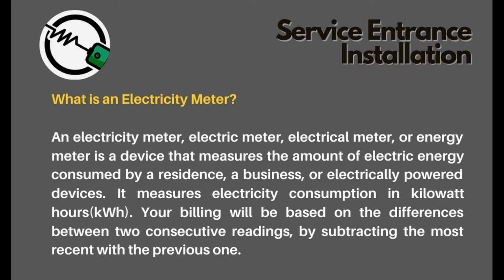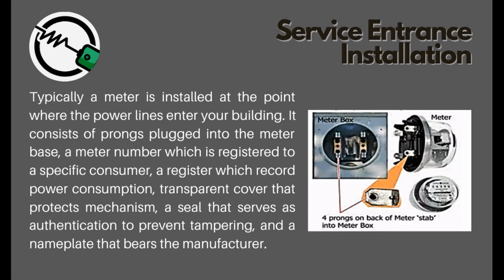Your billing will be based on the differences between two consecutive readings, by subtracting the most recent from the previous one. Typically, a meter is installed at the point where the power lines enter your building. It consists of prongs plugged into the meter base, a meter number which is registered to a specific consumer, a register which records power consumption, a transparent cover that protects the mechanism, a seal that serves as authentication to prevent tampering, and a nameplate that bears the manufacturer.